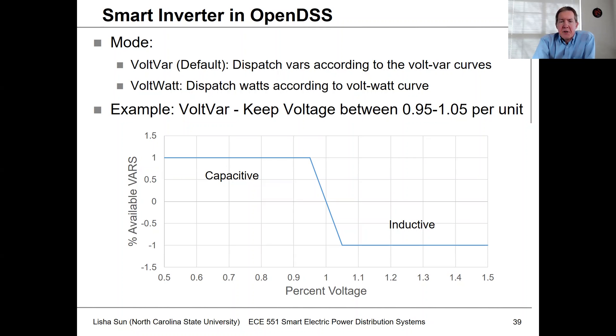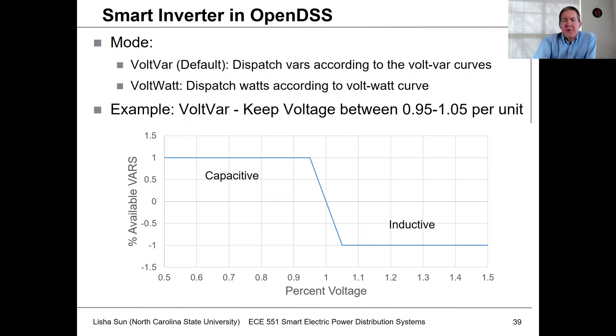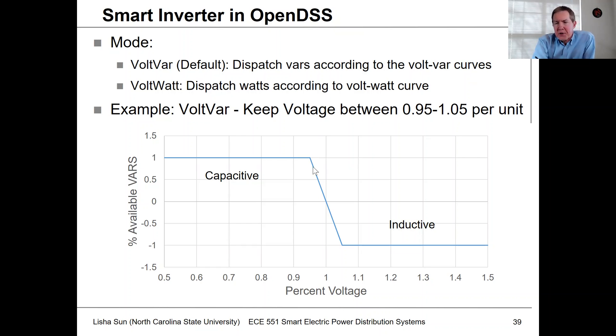We can set this up in terms of having volt-var support through injecting vars to help control voltage. There's also other functionality like a volt-watt curve, where if the voltage gets too high, we can start to curtail output. In this example, we'll choose a simple droop curve for volt-var control, designed to keep voltage between 0.95 and 1.05 per unit.